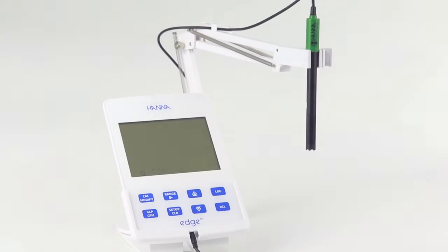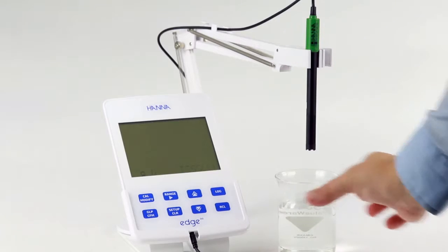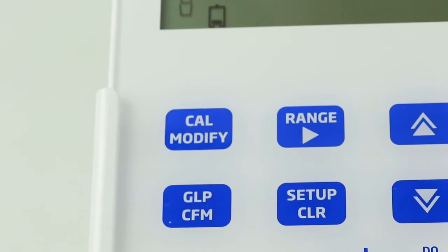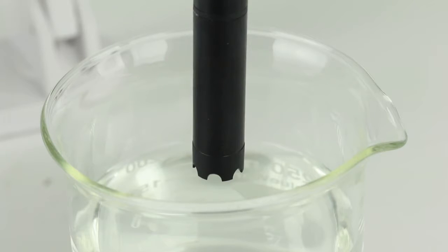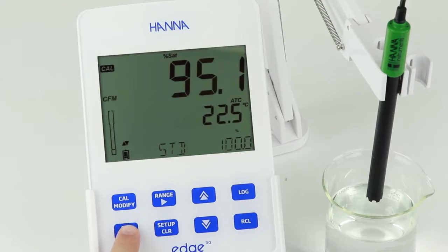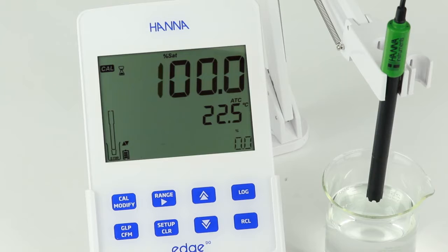To calibrate at 100%, prepare a beaker filled with water. Press Cal and hold the probe just over the beaker with water. Make sure you don't submerge the probe. Once the reading is stable, press Confirm to accept the calibration point. Edge is now calibrated to 1 point. If desired, press Cal to exit. Otherwise, we can proceed to the next calibration point.